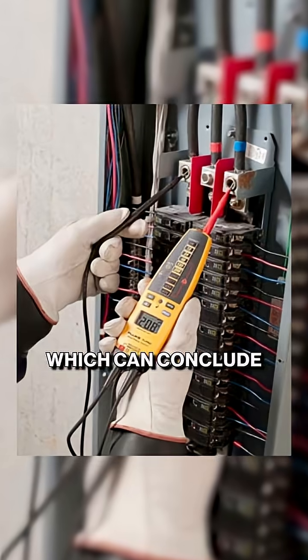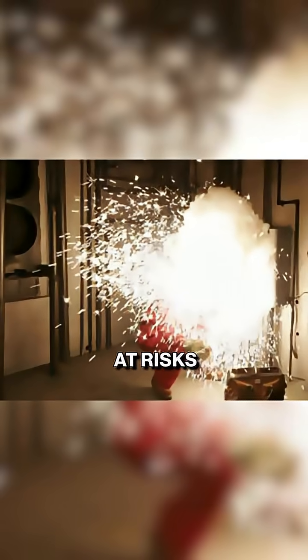But here's the difference: at Bowtie Engineering, we don't just hand you pictures. We combine thermal scans with inspections, CT measuring, and voltage drop measuring, which can conclude the reason for the heat. Some branch connections can be addressed on the spot. That way, you're not just looking at risks, you're eliminating them.